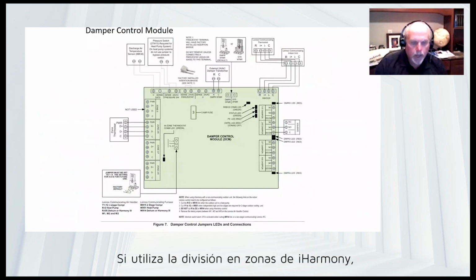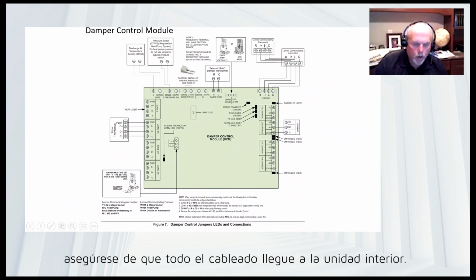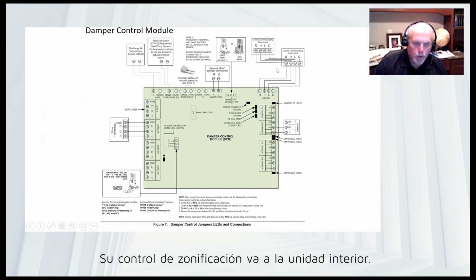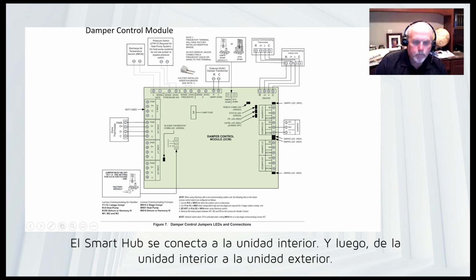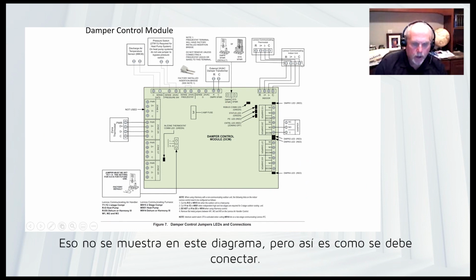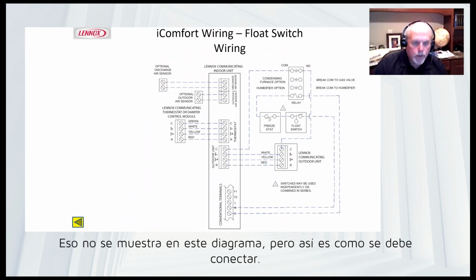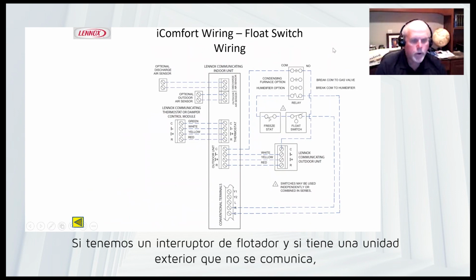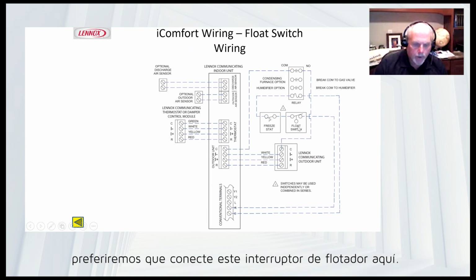Okay, if you use iHarmony zoning, just make sure that all wiring pulls to the indoor unit. Your zoning control goes to your indoor unit. Your thermostat or smart hub goes to the indoor unit. And then from the indoor unit to the outdoor unit. That is not shown on this diagram, but that is how we would wire that.